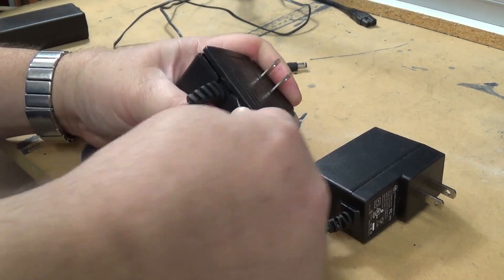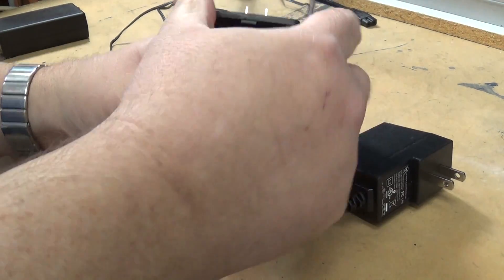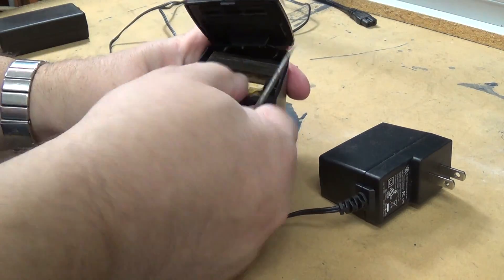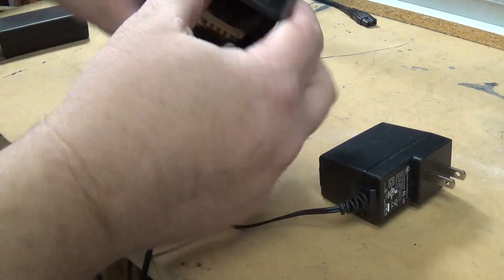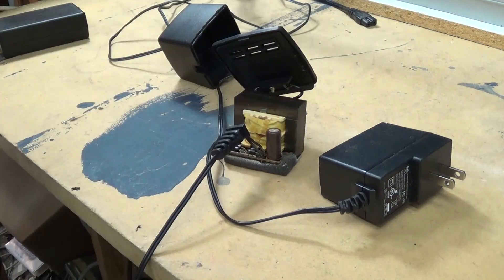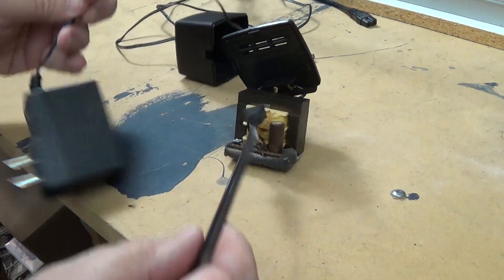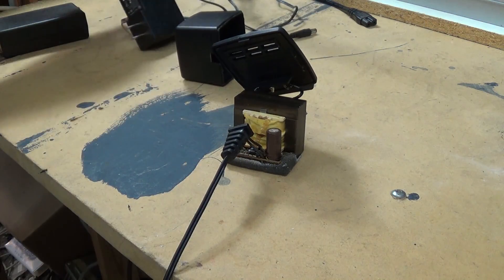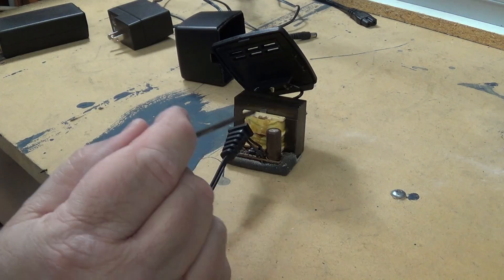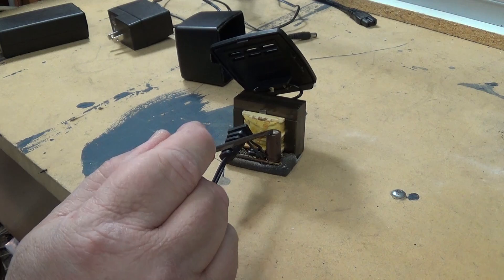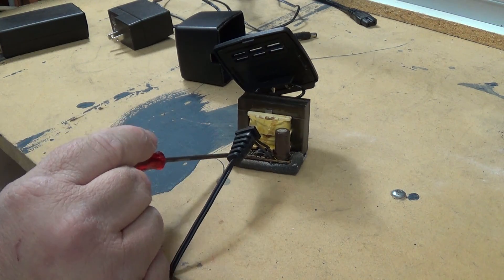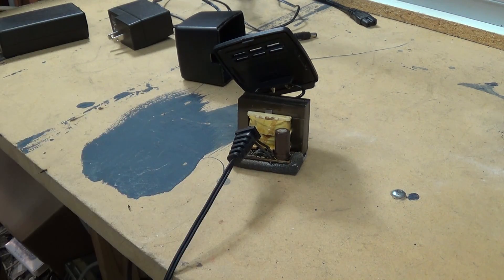And what we're going to find is we're going to find a single capacitor inside here, a big transformer. The unit comes apart just like that. Well what's going to be the point of failure on this unit? It's going to be this capacitor. So we're going to change this capacitor and that's the purpose of this video.